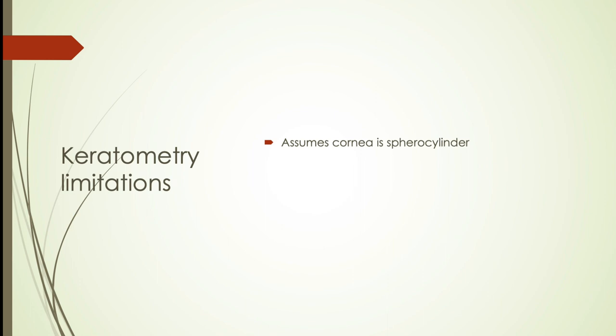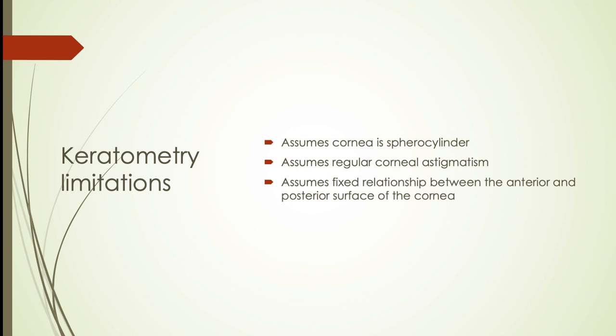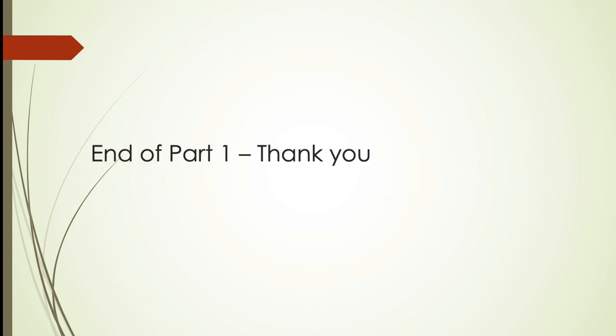The limitations of the keratometer are as follows. First, it assumes the cornea is sphero-cylindrical with regular corneal astigmatism, and hence can give erroneous readings or totally miss irregular astigmatism. Second, it assumes a fixed relationship between the anterior and posterior corneal curvatures, which is why keratometric values are unreliable in patients who have undergone laser refractive procedures.